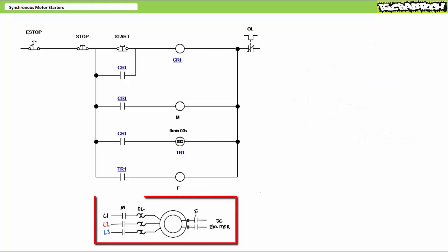The primary circuit consists of the M stator contactor in series with the overload on the stator windings and DC rated field contactor F on the rotor. Key to this particular application is the controlled closure of the F field contactor. We first want to close the M contactor and energize the stator with the field contactor open, such that the amortisseur windings in the rotor are given a chance to accelerate the rotor to near synchronous speed.